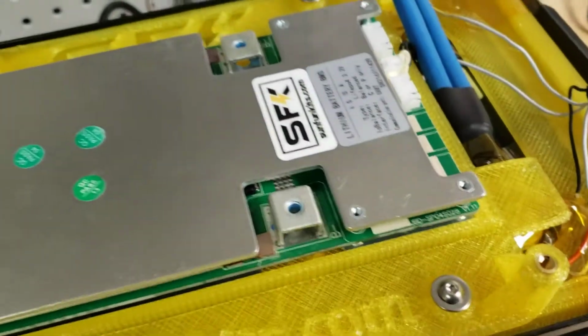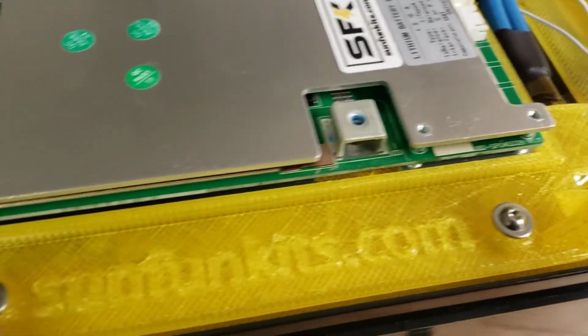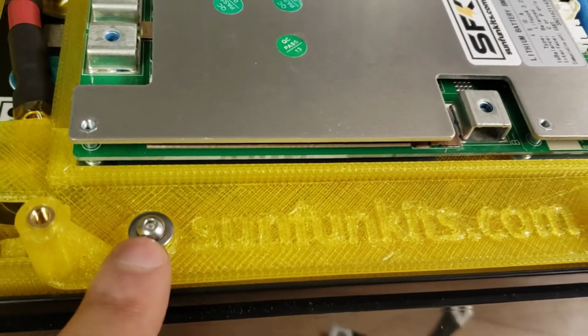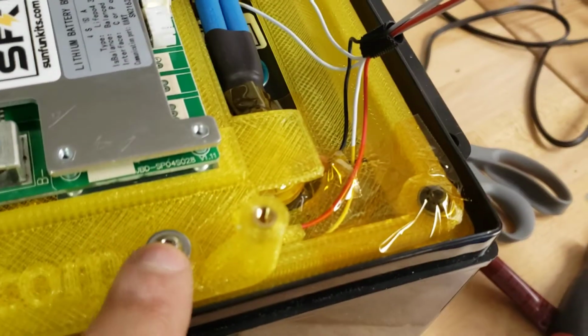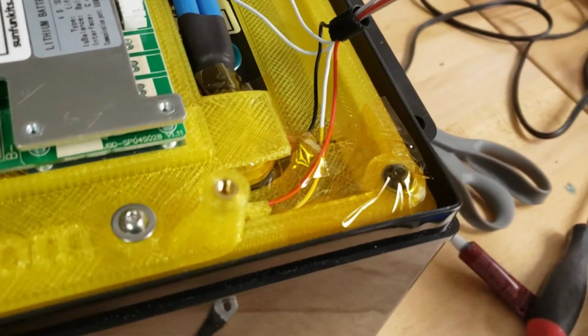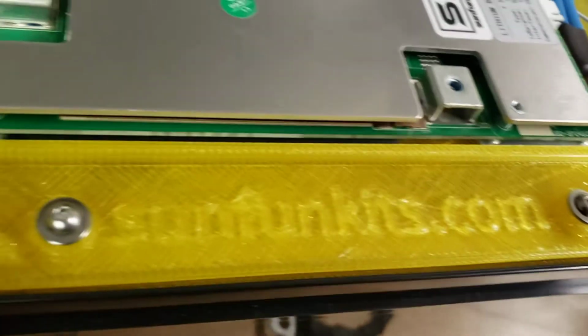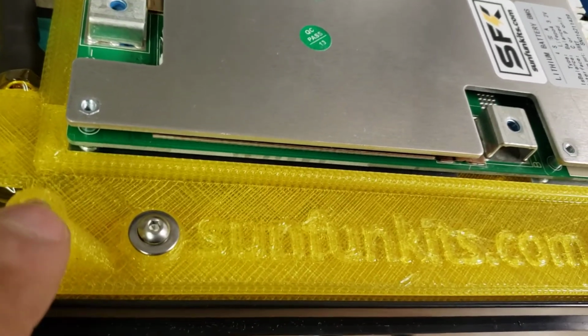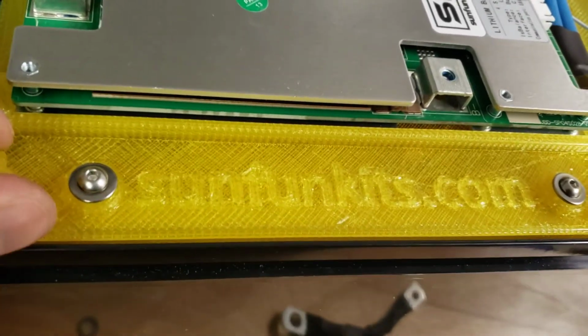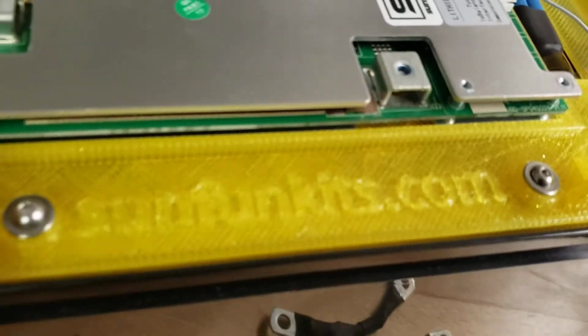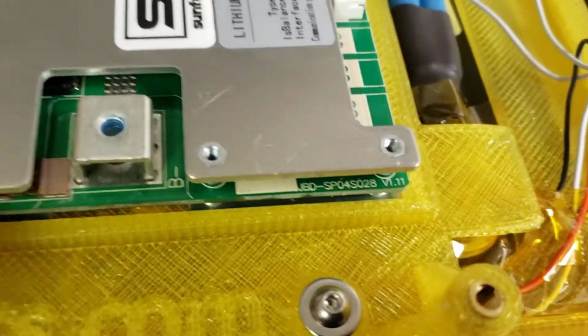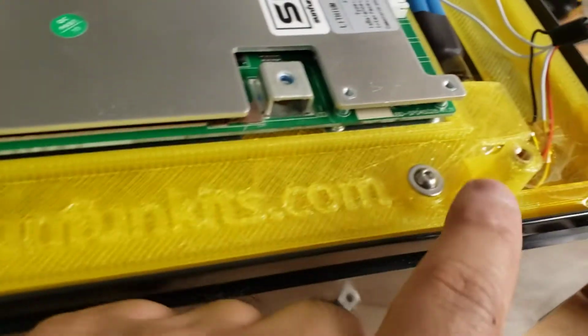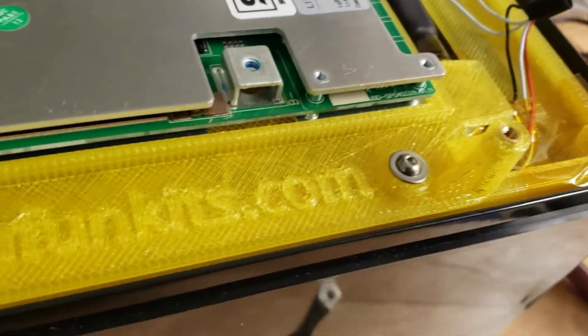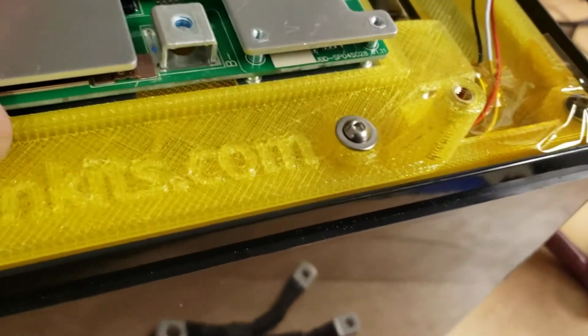Okay, now we have the BMS plate installed. It's extremely important you do not over tighten these bolts; they just need a hand snug fit. If you torque them too much, you'll rip out the metallic brass insert from the plate itself, and the plate will need to be replaced. So please be careful when mounting these - do not over tighten, just snug will be sufficient.